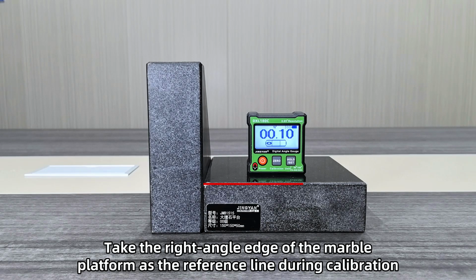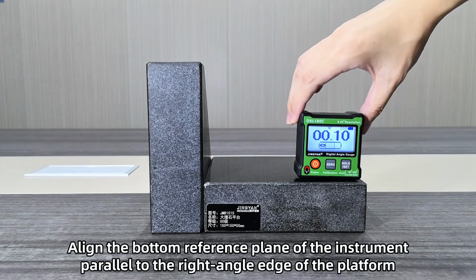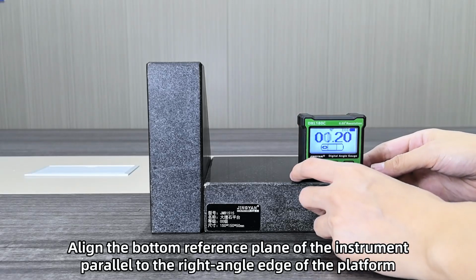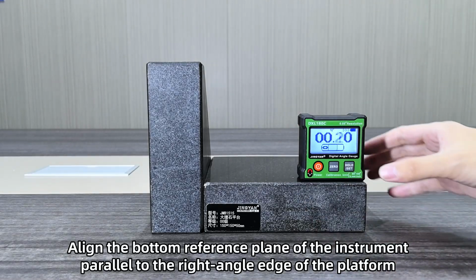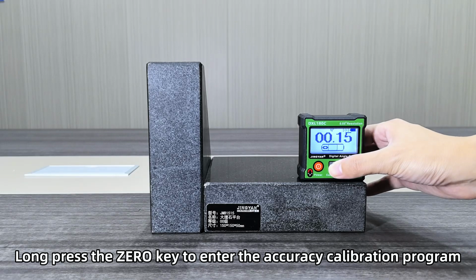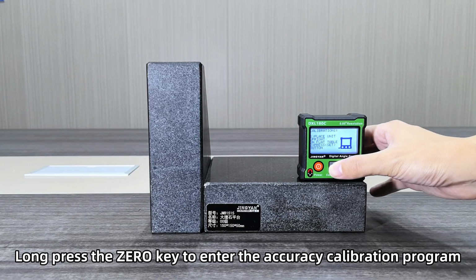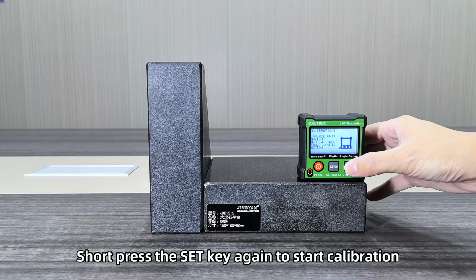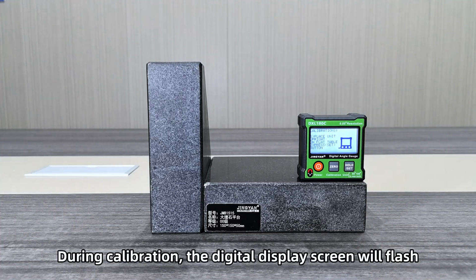Take the right angle edge of the marble platform as the reference line during calibration. Align the bottom reference plane of the instrument parallel to the right angle edge of the platform. Long press the ZERO key to enter the accuracy calibration program. Short press the SET key again to start calibration. During calibration, the digital display screen will flash.